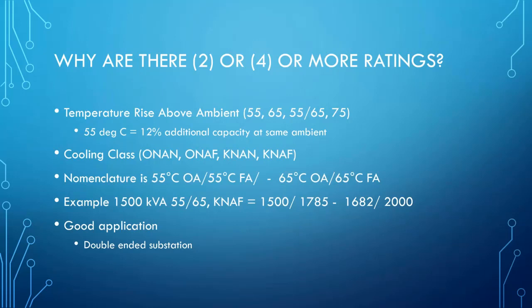Not only is it acceptable, there are now transformer manufacturers going to 75 degrees C and higher. And of course, your top end rating on that transformer is 2000 kVA. That's with the fans on and allowing the temperature to rise 65 degrees C above ambient. And where is this beneficial? The greatest application I can think of is in a double-ended unit substation.